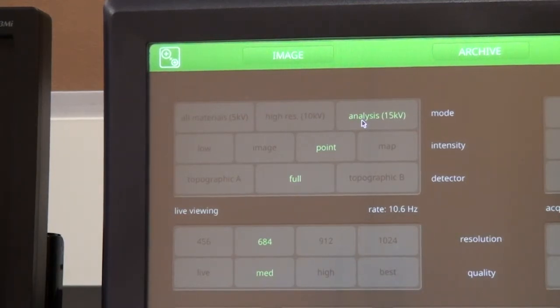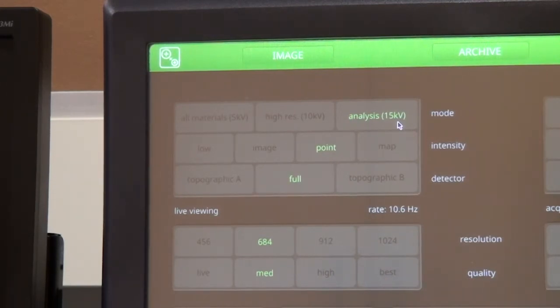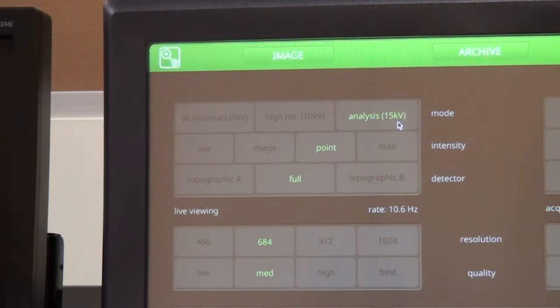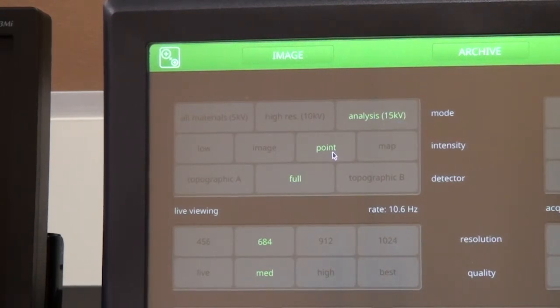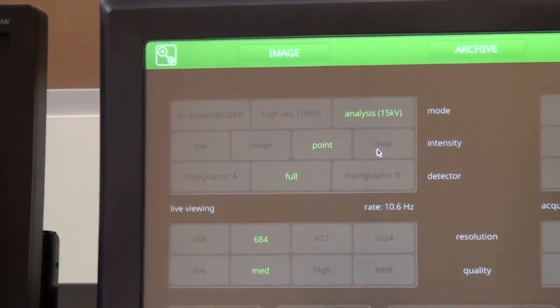If the energy of the electron beam is less than the ionization energy of the inner electrons, then X-rays will not be generated. So 15 kV is the best option if we want both imaging as well as EDS analysis.